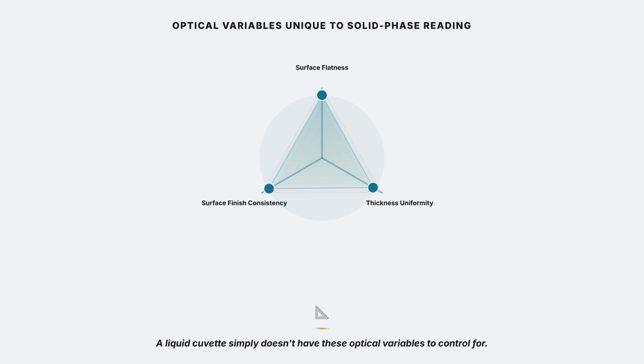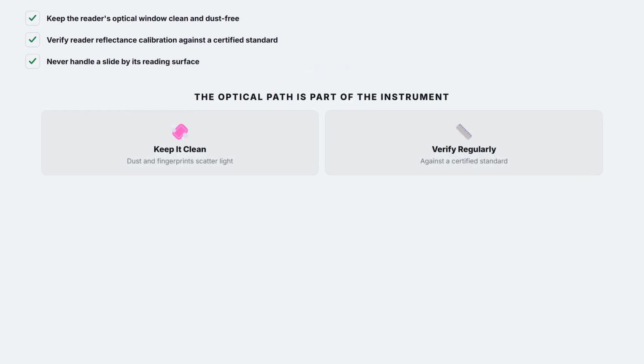Keep the reader's optical window clean and free of dust or fingerprints. Verify the reader's own reflectance calibration against a certified reflectance standard per the manufacturer's schedule. And never bend, fold, or handle a slide by its reading surface before or after measurement.